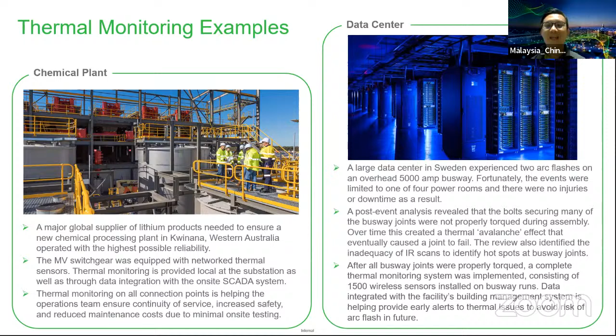So another part of this, besides thermal monitoring, is breaker settings. Breaker setting is not new. In Malaysia, we use something called a switch disconnector, not a full ACB, and the tripping is actually controlled by a protection relay or OCR — some people call it OCF.